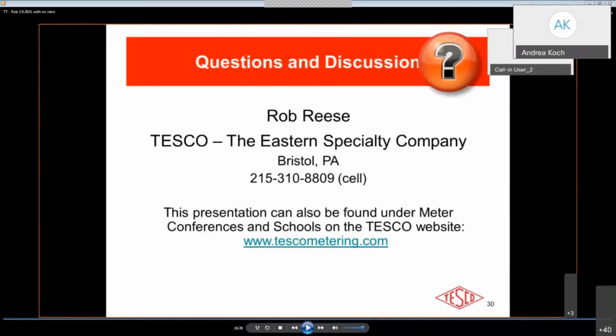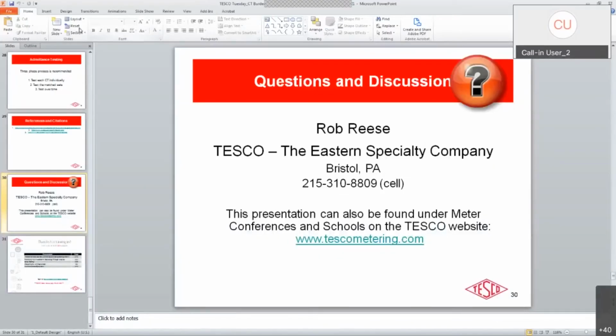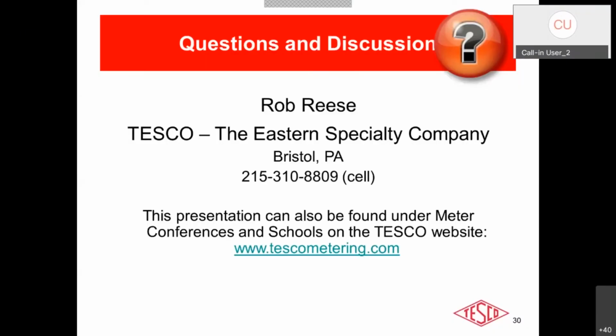Let's see, the next one coming in says, you said that admittance test needs to be analyzed. Is there an MS value that would indicate the CT is bad? The answer to that is no. Unfortunately, the answer is no, because there are so many different CT manufacturers that have produced so many different model numbers of CTs at various different ratios. There's not one millisiemens value that you can hone in on and say, oh, that's good or that's bad.